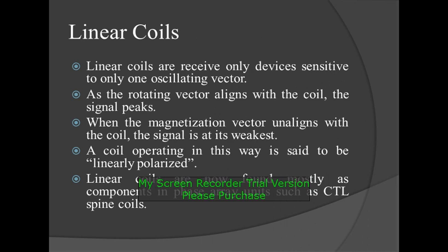Linear coils are receive-only devices sensitive to only one oscillating vector. As the rotating vector aligns with the coil, the signal peaks. When the magnetization vector misaligns with the coil, the signal is at its weakest. A coil operating in this way is said to be linearly polarized. Linear coils are now found mostly as components in phased array units, such as CTL spine coils — that is, cervical, thoracic, and lumbar spine coils.